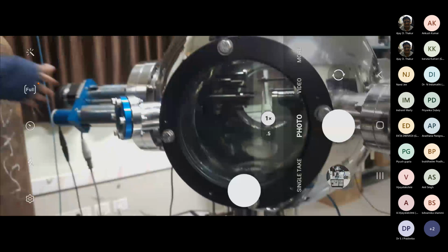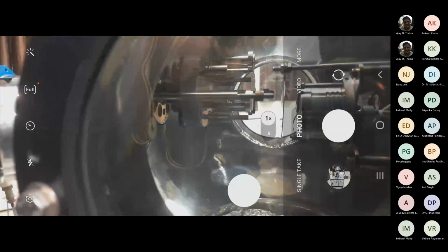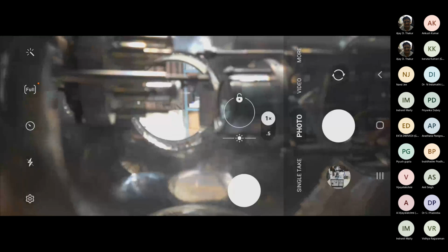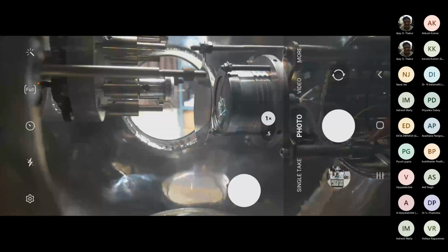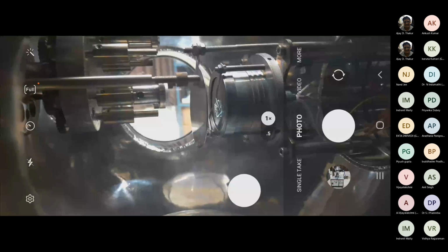Okay, so inside the circular part on the left hand side, you can see three protruding cylinders. So they are basically target holders. And on the right hand side, you have the substrate holder, which is also the heater. So the big cylinder on the right hand side is the heater. And you can also see a substrate which is pasted using silver paste. Yes, sir. This silver paste will survive at about 800 degrees C without really degrading. So this is the inside of the chamber.